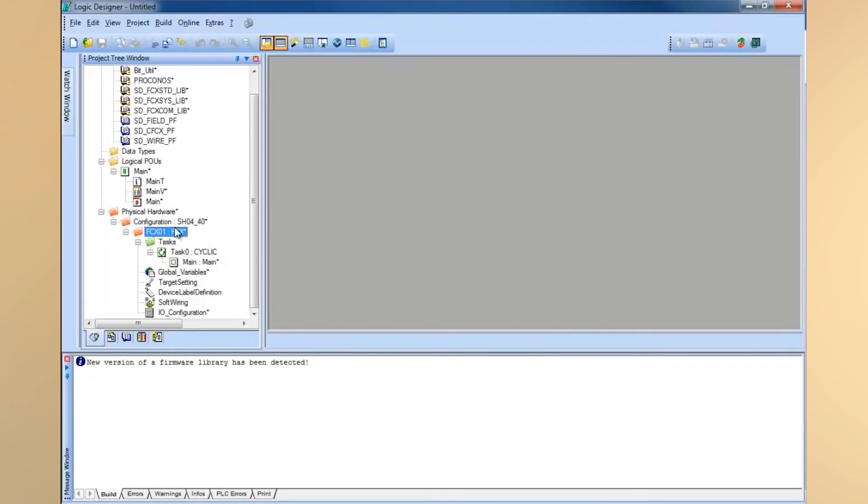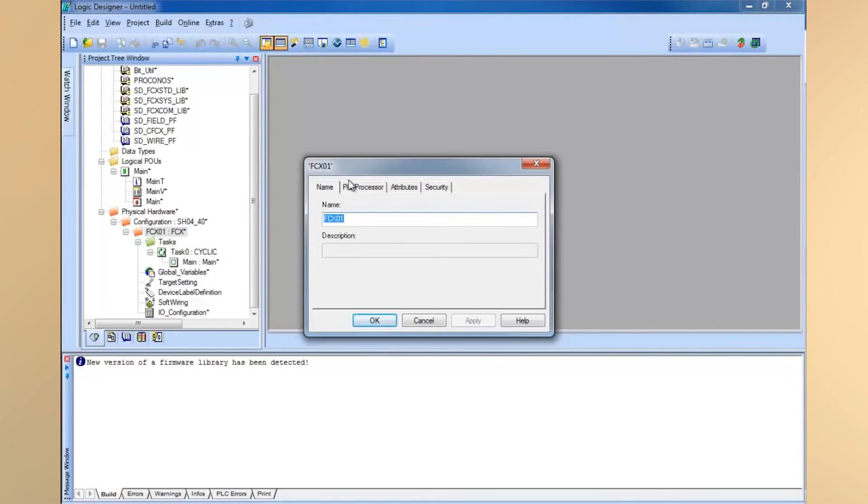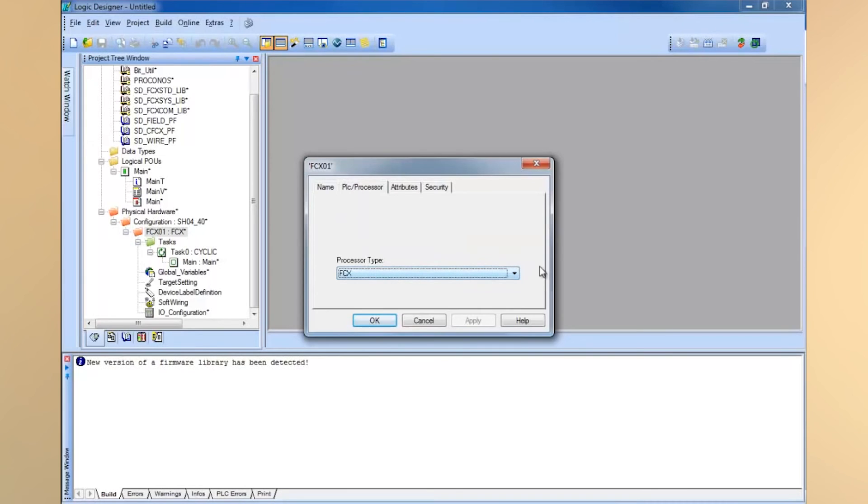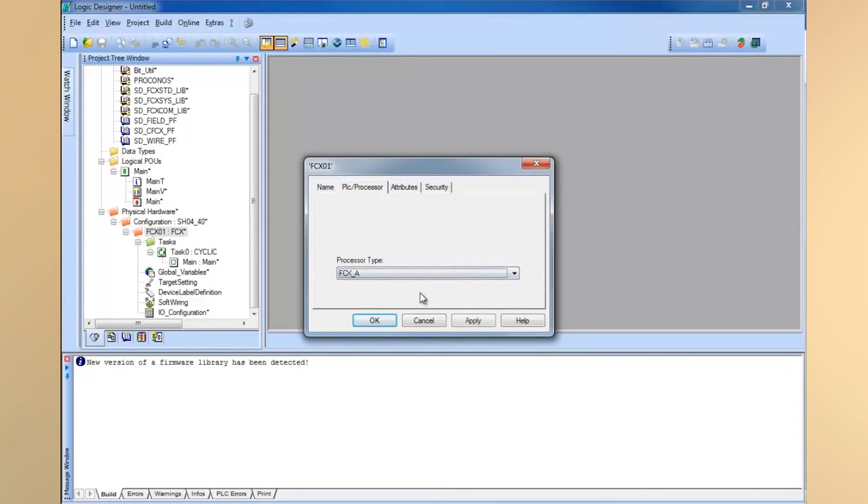The next thing you should do is look at the FCX setting here. You want to make sure you're going to use the correct processor for that as well. Select that, right click on it, and then select the PLC processor. Now you're going to select the proper processor. The FCJ and FCN use a different processor than the FCN RTU. But in this case, it doesn't matter. You can use FCX or FCX_A. This PLC setting really is just setting a memory size of how many objects you can create or tag names, POU names that you can create with the controller.